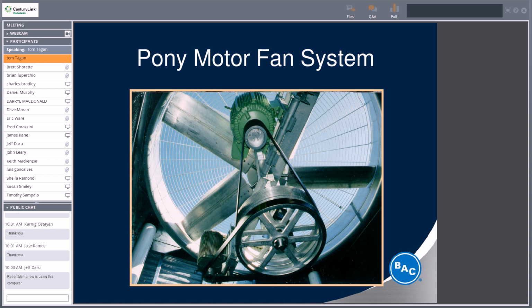Pony motor, years ago, this was the poor man's VFD. We'd supply a motor that was approximately a third of the total fan motor, so that if 75% of the year you're running at reduced capacity, we can run at that smaller horsepower. But these systems have kind of been replaced by the VFDs since the cost of VFDs has come down significantly since we were using pony motors.